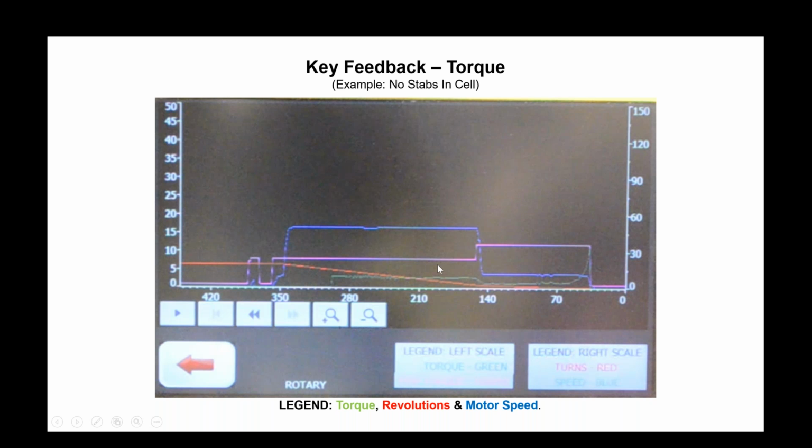So even there, reliability wise, people are utilizing this as a maintenance tool, right? The grease may degrade over time, and the torque requirement would go up. Eventually this torque requirement gets into this pink purple line, and it's going to trip, right? Because this is 3 or 4 foot-pounds and this is 6 or 7. We don't want to allow more than 6 or 7 here because we know that's abnormal. So that's the way the torque monitoring works as well.